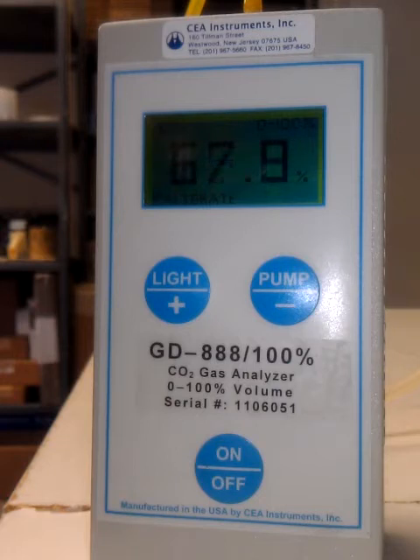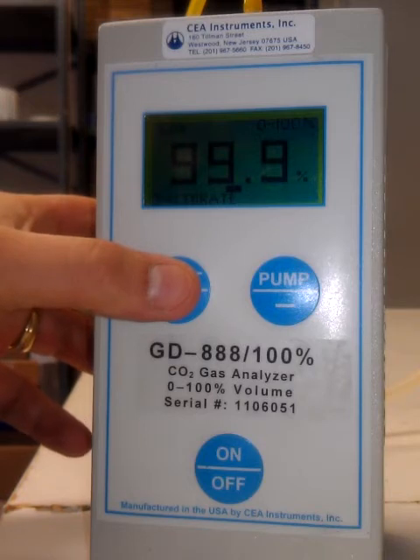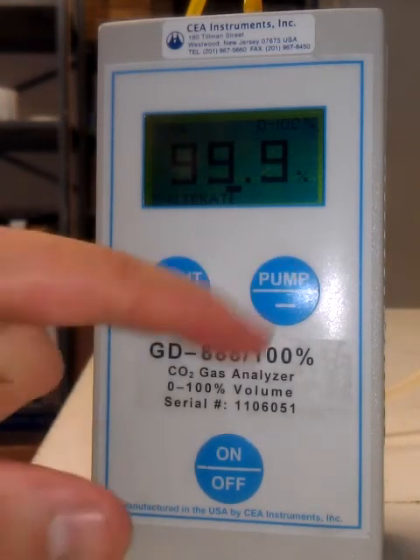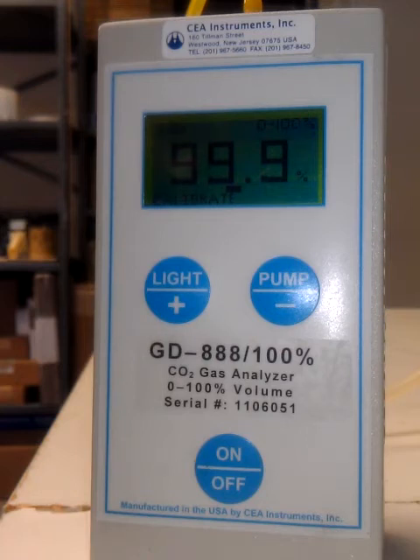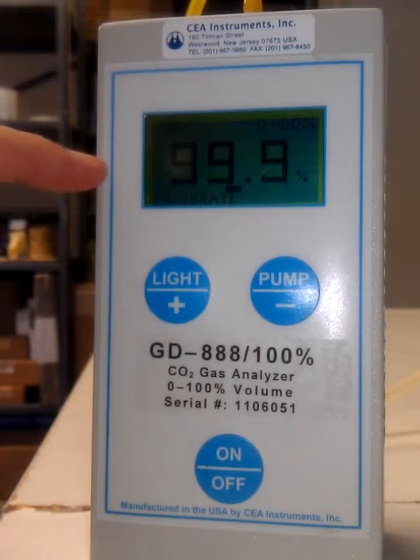It should go to 99.9, but however, it sometimes takes a little bit to get there. It could sometimes hit it and settle down, so you should wait sometimes even a minute to make sure it stays at 99.9. If it doesn't, or if it goes down, then you would hit the keys up and hold, and it climbs, or down. You would never really do down because it won't go past 99.9. So if it's reading 99.4, 99.6, and it is not bouncing up and down, and it's staying in one spot, you get it to read 99.9.